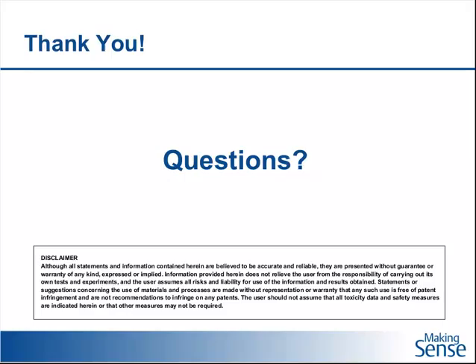The next question: Is Copeland going to offer fractional scroll compressors in the future? We've actually engaged with a few of our OEMs that have requested this, and we've kicked off a development program, challenging ourselves to develop scrolls all the way down to three-quarter horsepower. That will extend our range significantly from the one and three-quarter horsepower that we have today down to that three-quarter horsepower range. We see this as a key technology that will allow OEMs to meet the DOE regulations, potentially allowing them to meet that regulation with only a compressor change — moving from a hermetic compressor to scroll compression technology.